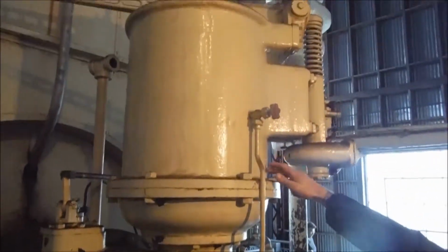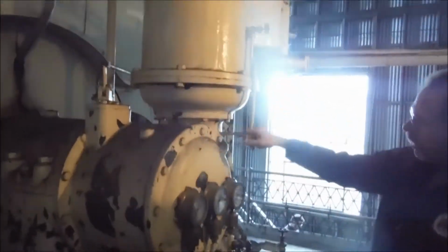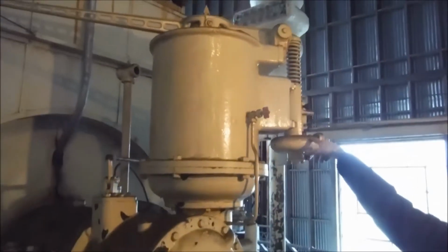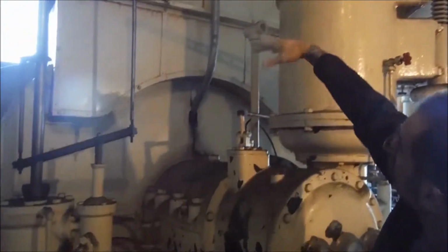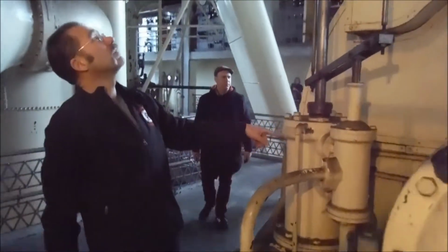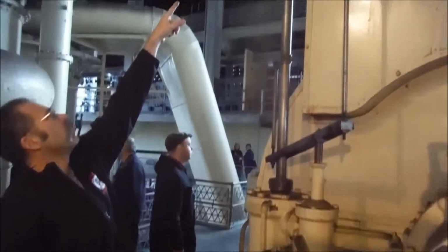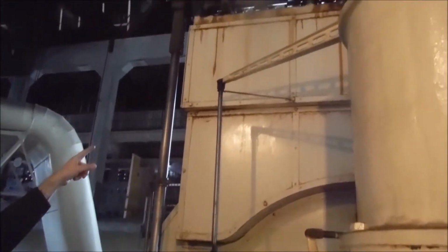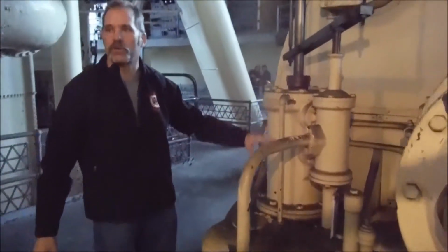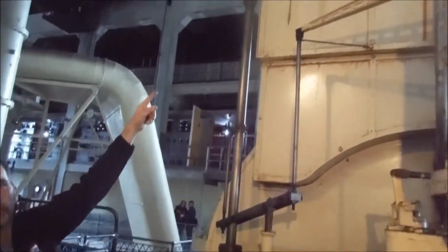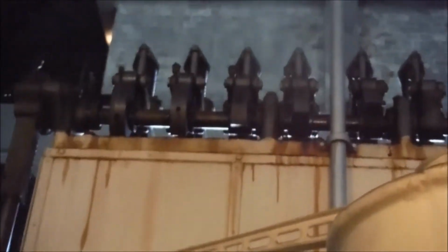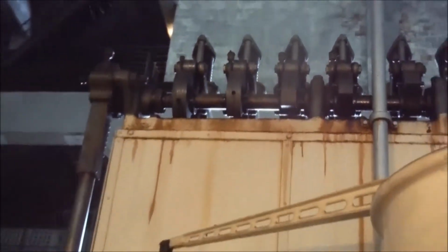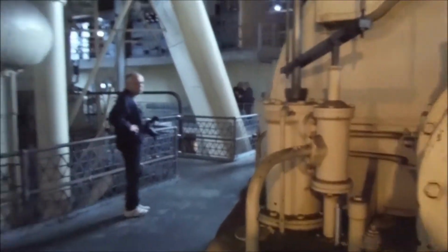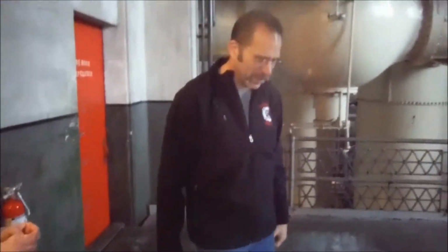And this, I'm absolutely sure, has the spring mechanism. Oh yeah, there it is. So turbine rotation activates a mechanism in here, causes that beam to be tilted. This probably has oil pressure under it, and then this rod going up and down through that rack and pinion would operate the steam admission valve. Probably controlled by this linkage and physically lifted by oil pressure under a piston here, because you need significant force to operate those valves. So a mechanically controlled hydraulic piston off the lubricating oil system through the turbine, operating the steam inlet valve, which is exactly how we did it in the Navy, really.